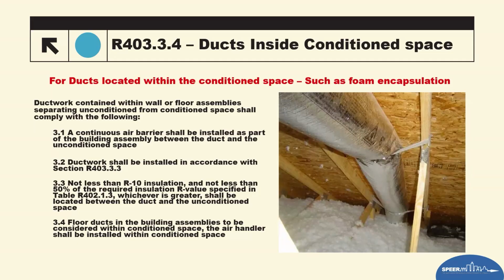As it says here, or at least 50% of the prescriptive insulation of that assembly, whichever is higher. So if we're looking at an R13 in the climate zone of Texas, and it's in a vertical cathedral, or on a vertical wall coming down from the attic above, if you're foaming, you've got to pull that duct away from the outside air barrier and put at least an R10 behind it. So you want to make sure those are done. You can't just foam around it and expect that duct to be up against an outer air barrier.